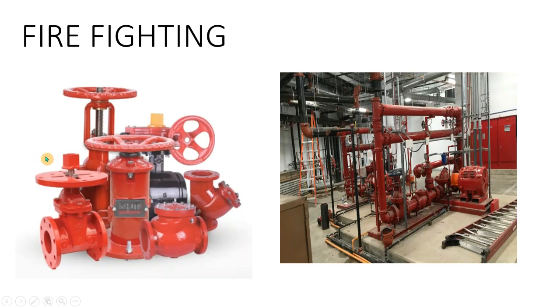The next one is valve. We have different kinds of valves and accessories available when it comes to firefighting, such as check valve, PRV, and gate valve. Typically we will not use gate valve in this trade. We will be using the OS and Y valve, which is the outside screw and yoke valve. That's a type of gate valve, but we cannot call it a gate valve - it is slightly different from the gate valve.